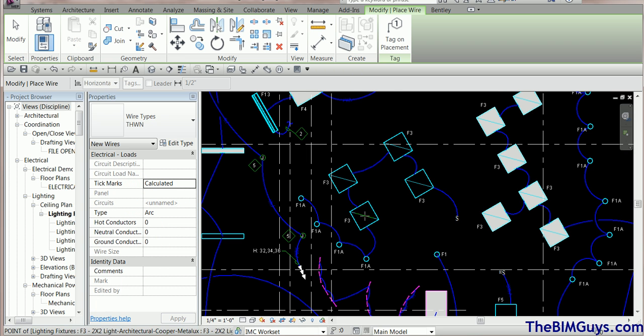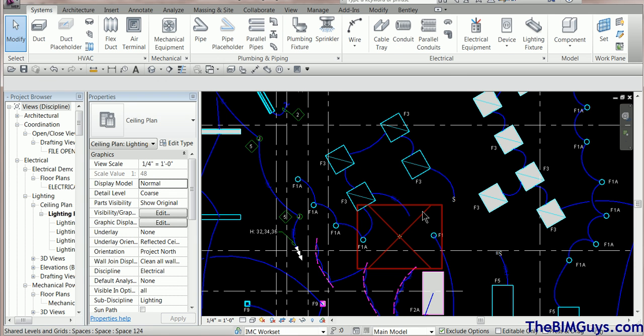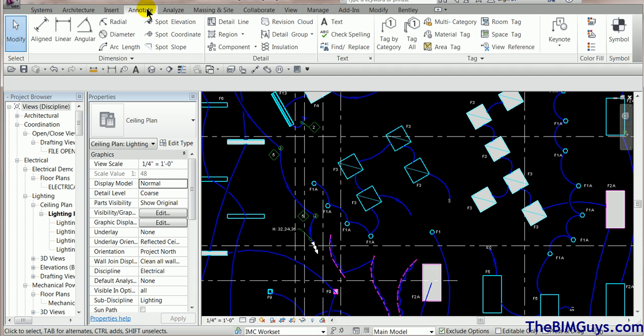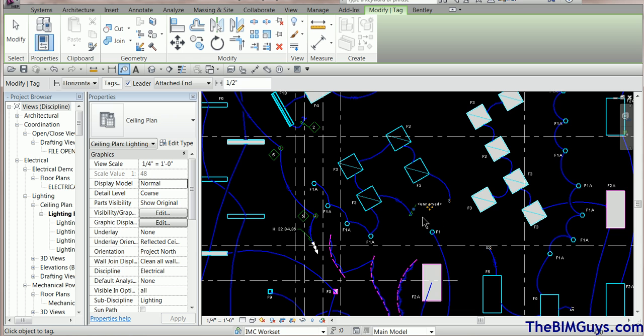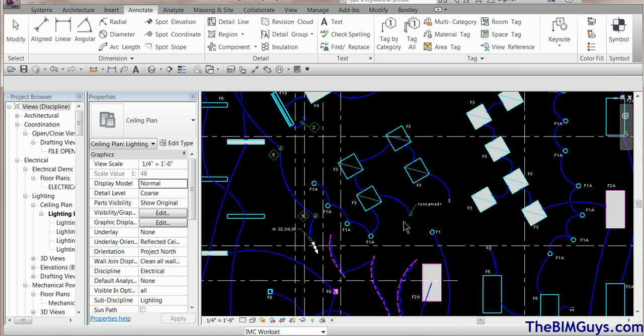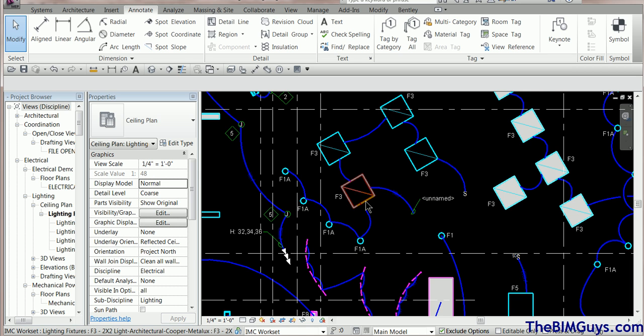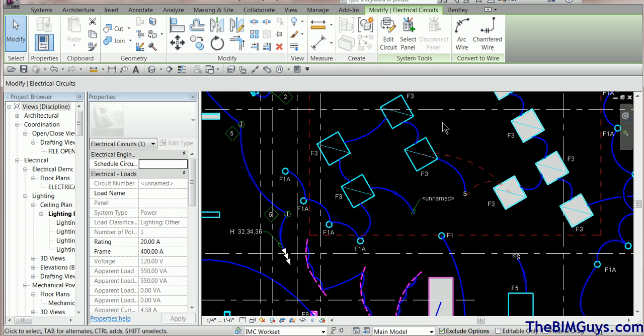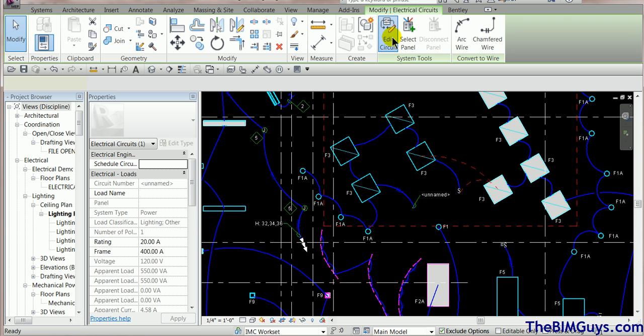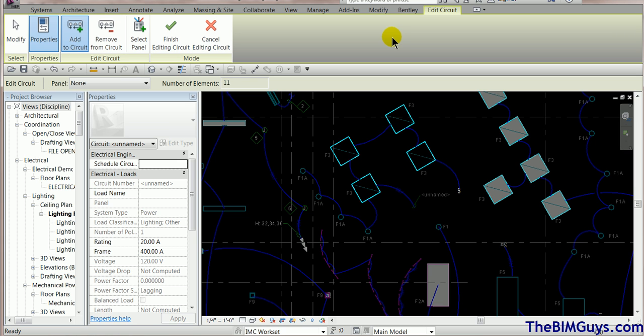I grab Wire, pick the connection, run it one-two, and see what we get. Notice there are a lot of ticks in there — that's interesting. Let's go to Annotate, Tag by Category, hover over it, and pick it — it says unnamed. Let's investigate what's happening with the circuiting. Hovering and hitting Tab twice fires up a selection; when I pick it and hit Edit Circuit, you can see it's not set to a panel.